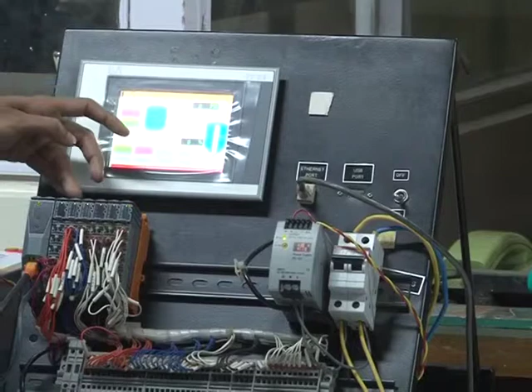And these are the modules. First module is the bus coupler module, as I already told you. Second is the power supply to give supply to this complete unit. Third module is the digital input module, this one is the digital output module, AI module, AO module, and last is the thermocouple module. As all the channels are currently open on the thermocouple, it is showing error.